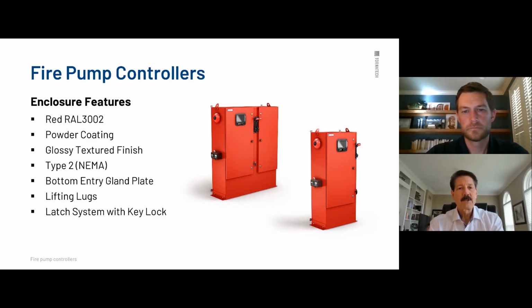The bottom channel irons that were mentioned, they're sitting there now, but if you wanted to ever gain an extra 3/4 to 1 inch, you can unbolt each side and flip them over and rebolt them in. What you'll do is lift the enclosure approximately 3/4 to 1 inch off the finished floor or a pad, if that's something you might need. Little things like that, you kind of learn in the field of what you can do. So thank you, Cole. Yep. Thanks, Marty.